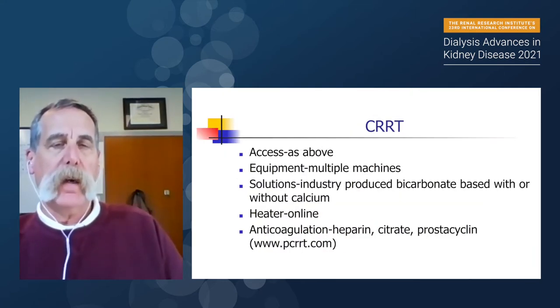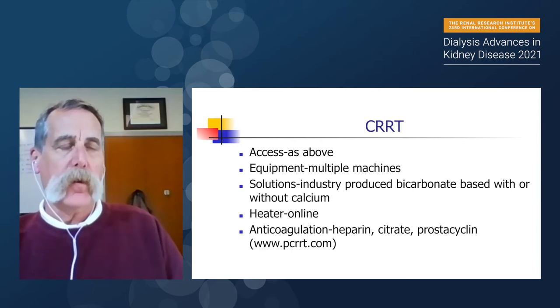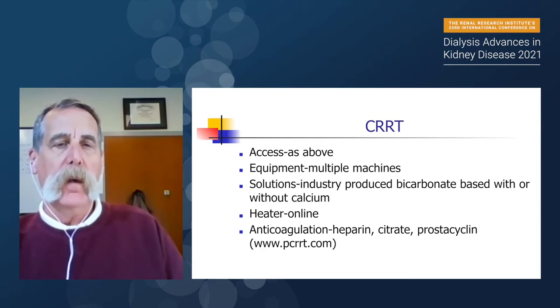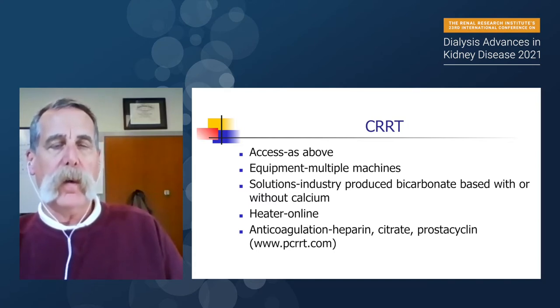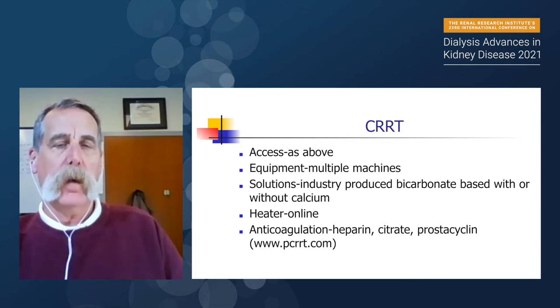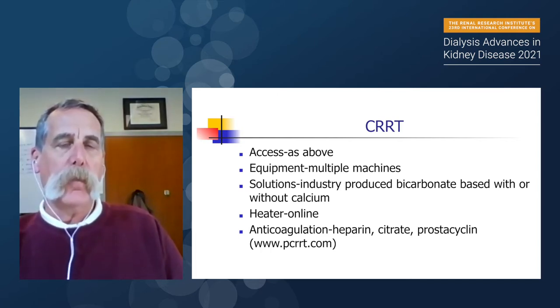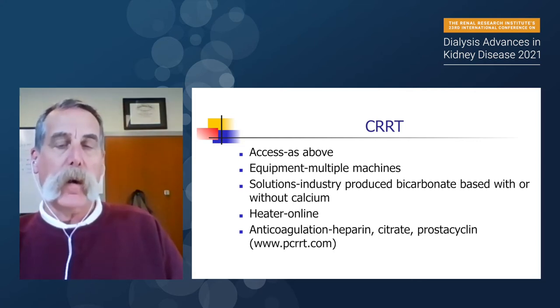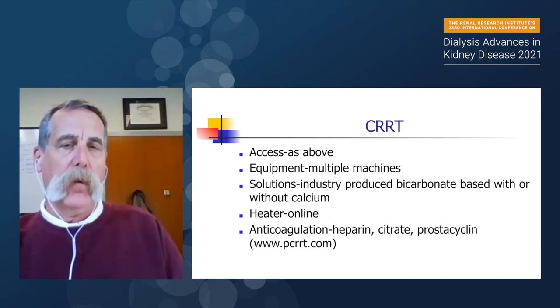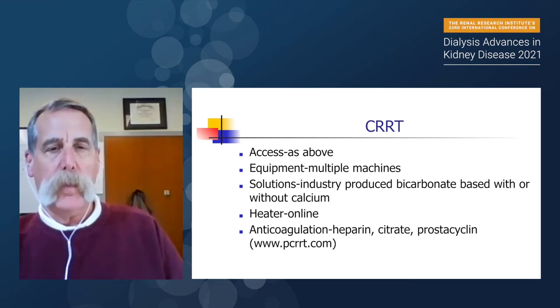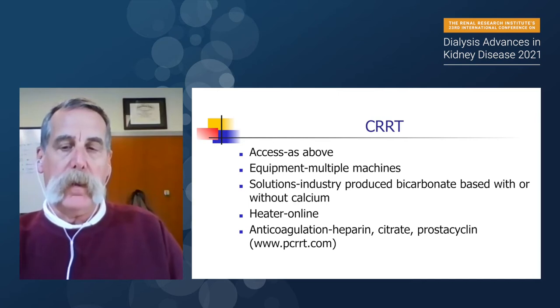CRRT has been around for about two and a half decades now, and I was very fortunate to be at the very beginning of that. Access is similar to hemodialysis. Various machines are available. Solutions since 2000 onward are bicarbonate-based with or without calcium. We are a citrate-based program, so we use calcium-free solutions. There's a heater online, which is usually not adequate for most patients, especially if they're small, and anticoagulation can be heparin or citrate across the circuit. For anticoagulation protocols, please refer to our website, www.pcrrt.com.